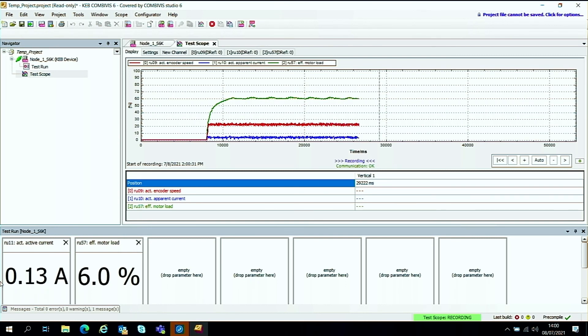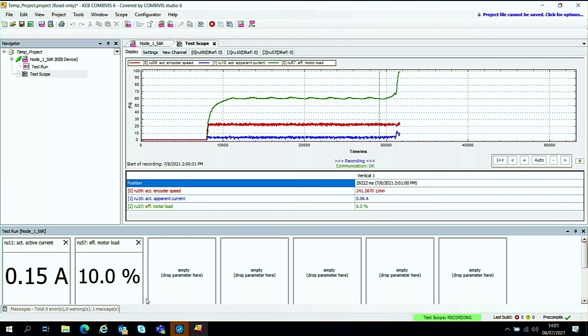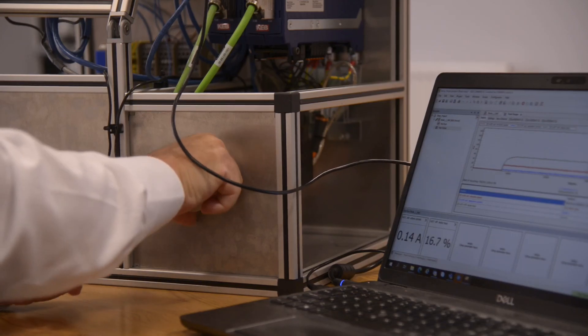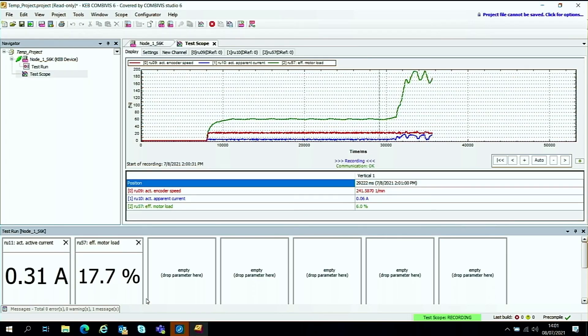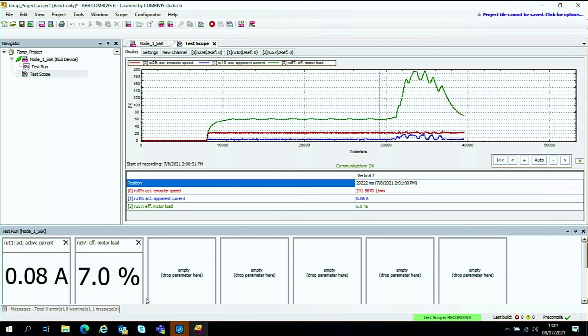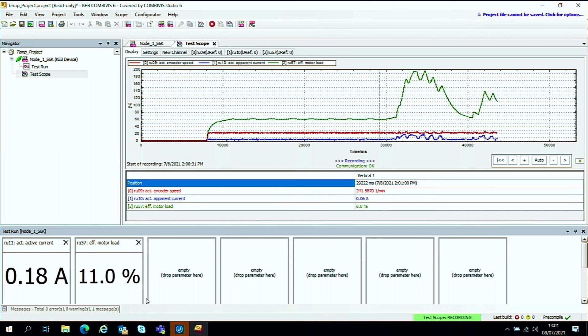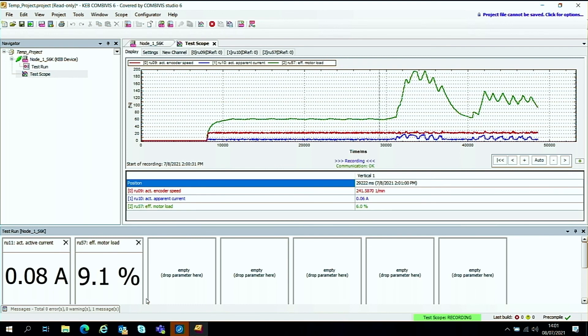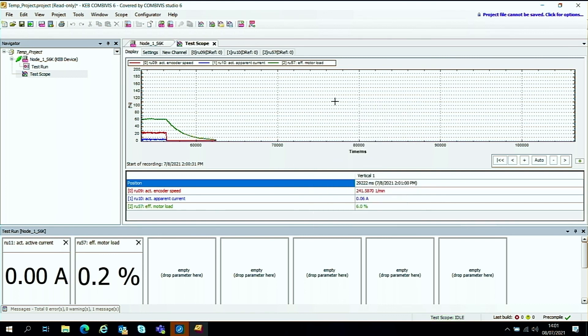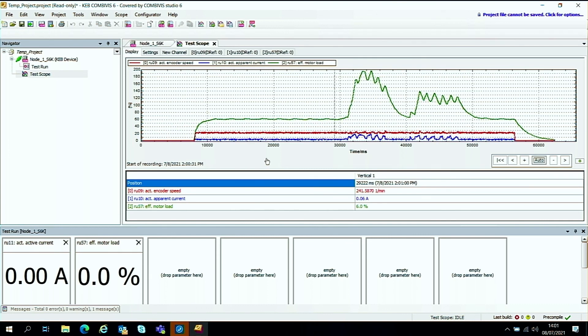Now what I'm going to do is because we've got this motor load, I'm going to just grab hold of it and see if I can put some extra load on it. And as you see, you can put some load on and then we can drop it down again. And hopefully you will see the values changing live as I grab the motor shaft here. To demonstrate the increased loading on the motor shaft. So I'll just stop that again. Take the scope here and I'll stop the scope from running.